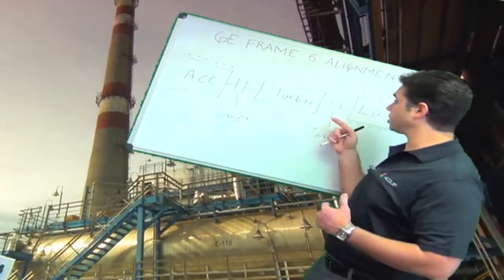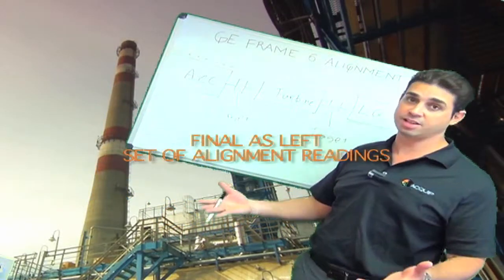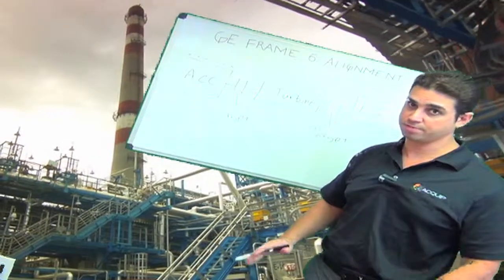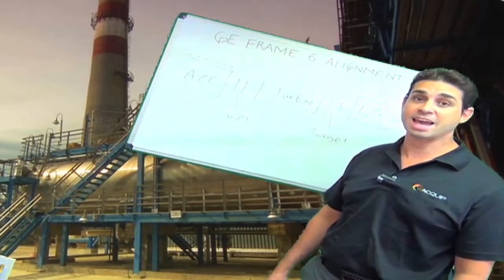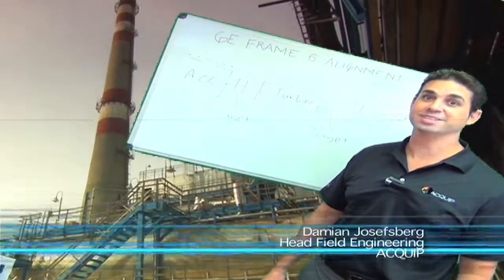At this point I'm going to take alignment readings at both the couplings and at all the other components to have a final as-left set of alignment readings, because I'm always going to end on a reading, never on a move. And that's how we complete a GE Frame 6 gas turbine alignment. I'm Damian Josephsberg from ACQUIP, and I'll see you next time.